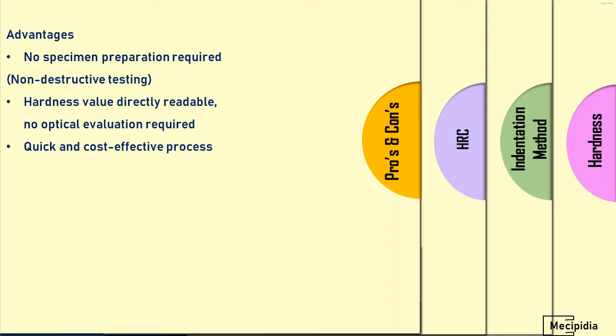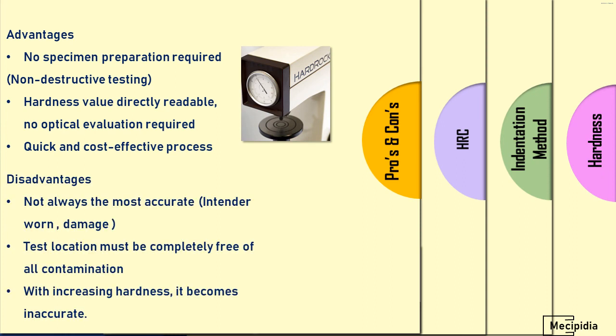First, no specimen preparation is required - it is non-destructive testing. Hardness value is directly readable; no optical device is required to evaluate the hardness. It automatically displays after the test because it is a differential depth method. The needle will display the hardness value. It's very quick and cost-effective.